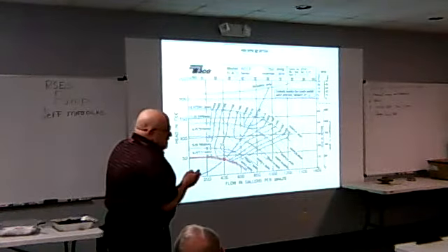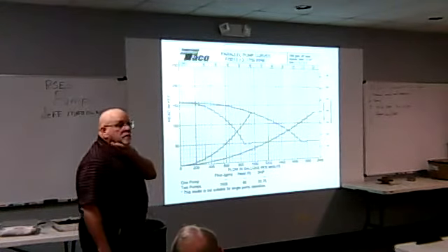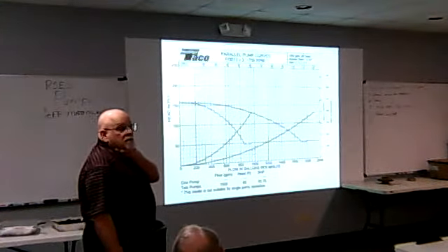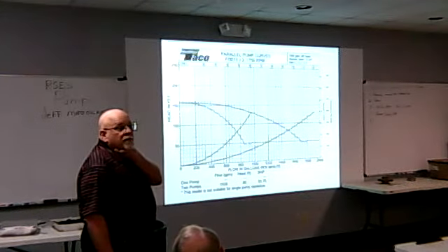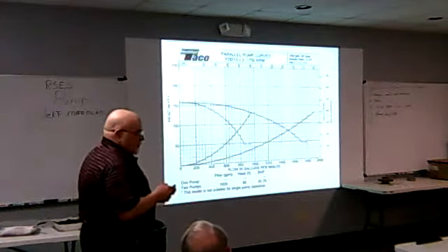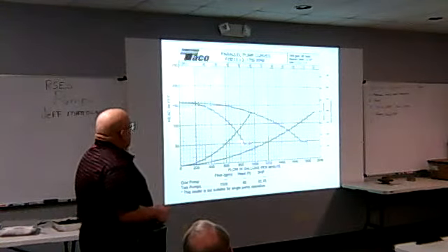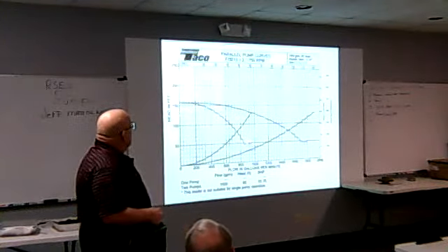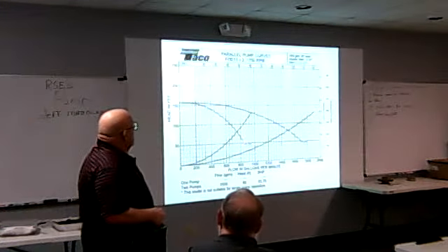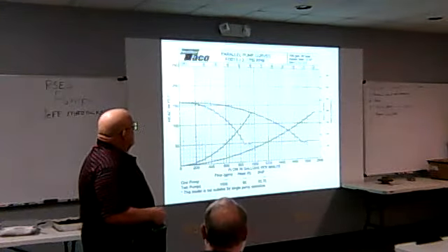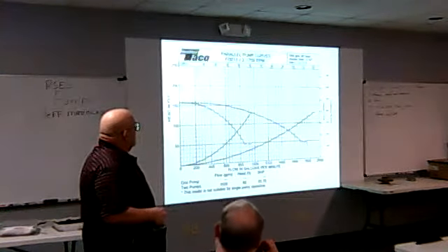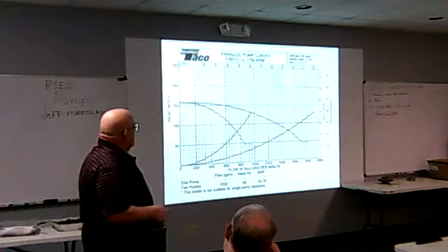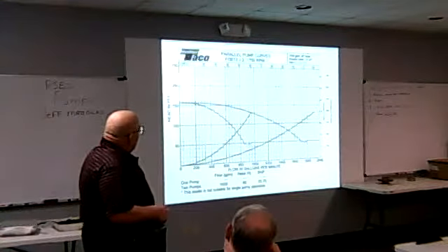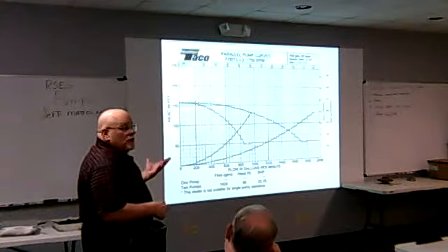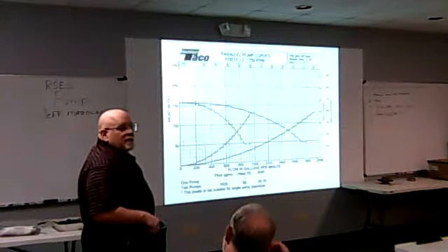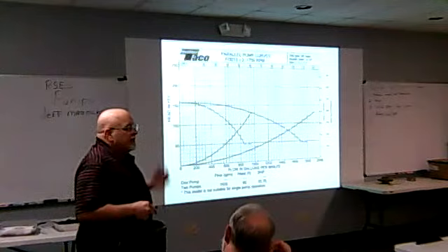All right. And again, can you back up 1 second? Yes, sir. Just for clarification purposes, your left-hand P1, P2 cutoff is what, 850 gallons there? Somewhere in that neighborhood? Correct. That's where it's going to stop. You're still going to pump the 850, and it's not going to go any higher than that at 50 feet of head. But if I go into parallel, I'm good, but this is a new system curve, just ignore it. Understood. But with my new flow, I can't get there from here. Non-existent, and you have to be careful about that.